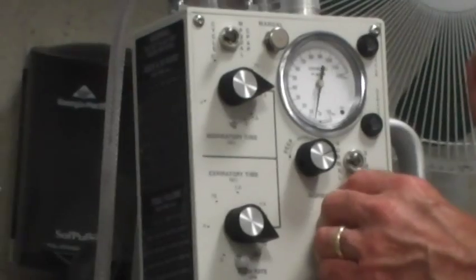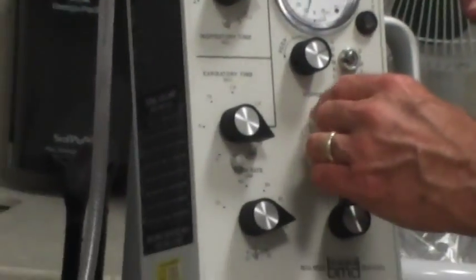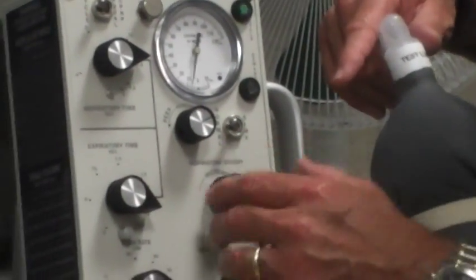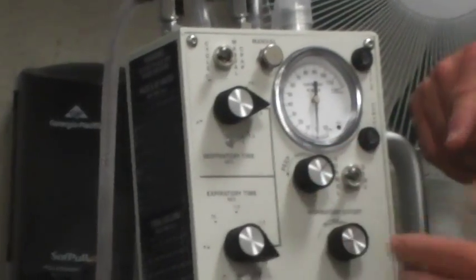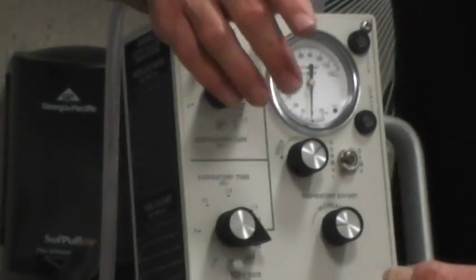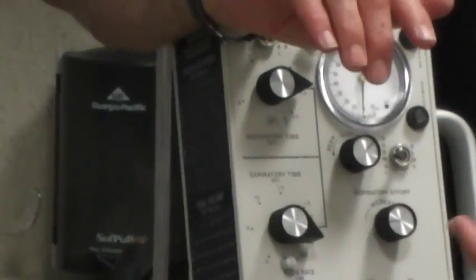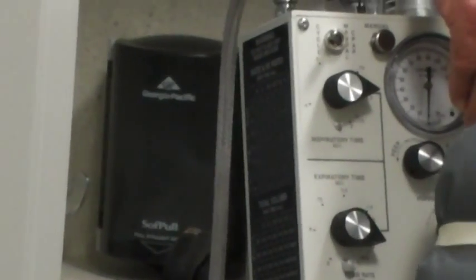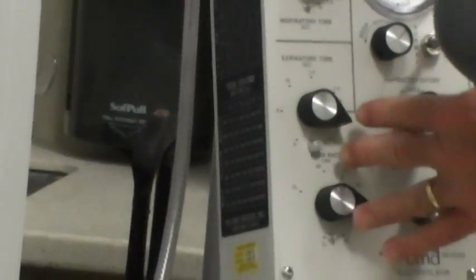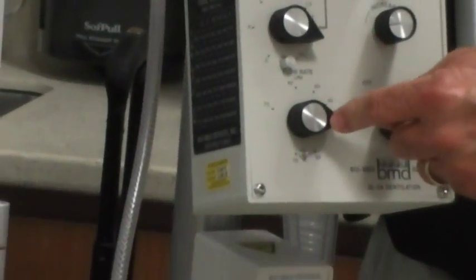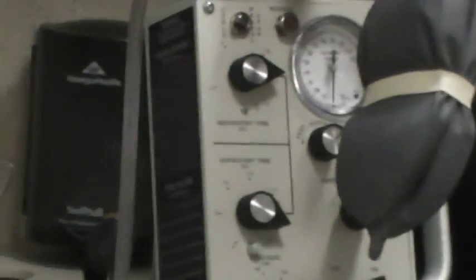One other thing, this is delivering a square wave pattern for the breath, which, in today's high-tech expensive ventilators, you've got a decelerating wave pattern, and it's more patient-friendly. So what happens is the patient's getting a lot more flow at the beginning of the breath, and it tapers off. If you put the same volume that they're on that vent, on this vent, they're getting their volume. The problem is they may not be getting it as fast as they want, because some patients really are almost air hungry and they need that decelerating wave pattern. We can kind of simulate it a little bit.